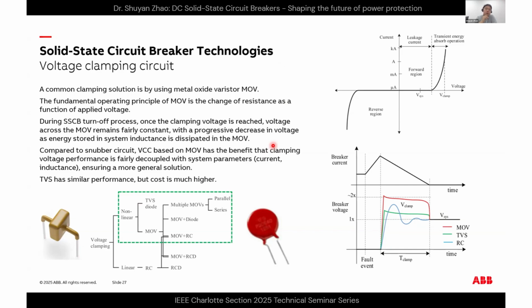So for this type of solid state circuit breaker, if we properly design the semiconductor and also the voltage clamping circuits, it can work properly almost forever - millions of operations, millions of fault events, or at least a few thousand to tens of thousand times of fault events.